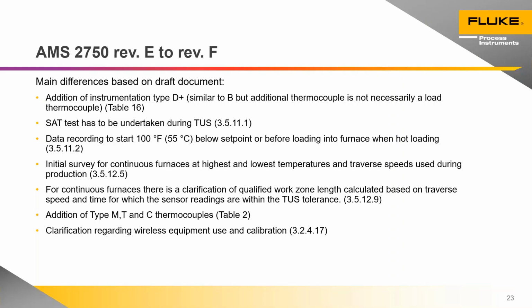The 18 pages of the report that you didn't see just now on the previous slides were actually a printout of the temperature readings for each of the thermocouples at each of the stabilization periods. And looking at this change on Rev F, we will be recording and reporting that data from a point 55 degrees below the set point so that we comply with Rev F whenever it is released. You know, it's not released at this point.